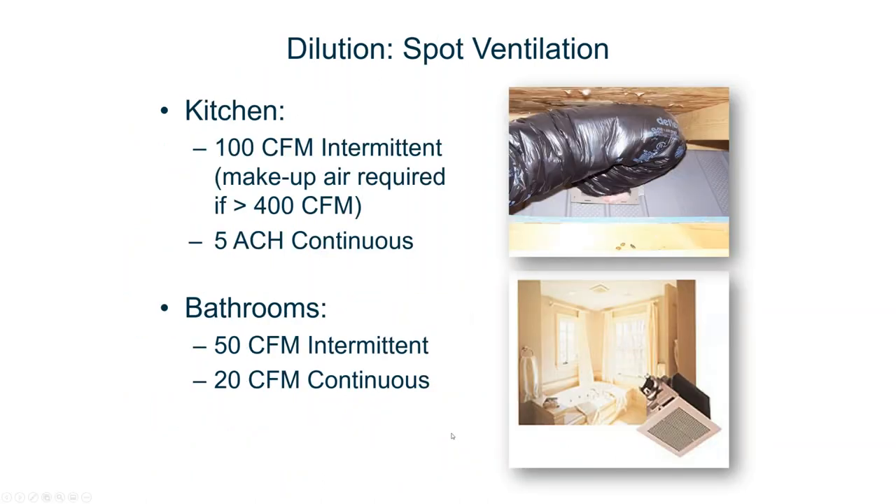Spot ventilation is really critical. The numbers are basic: it's 100 CFM. If it's an on-off switch, if it's continuous, it's 5 ACH. Research studies and expert friends at Lawrence Berkeley National Lab would tell you, you want a switch on higher level than just a continuous in a corner. If you get over 400 CFM on your intermittent exhaust vent or exhaust hood over your cooktop, you need a make-up air requirement. Bathrooms have to be 50 CFM.